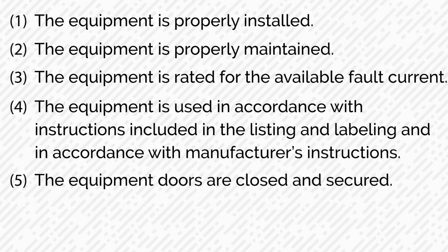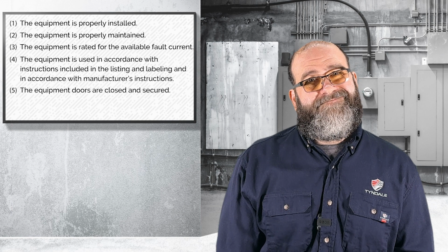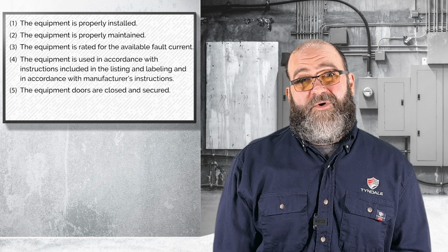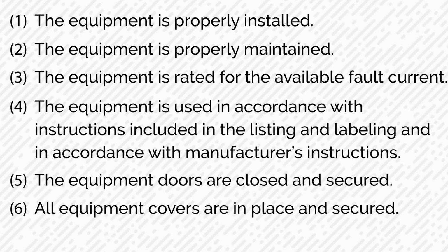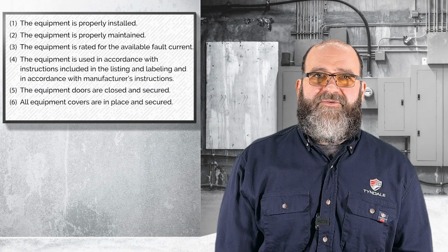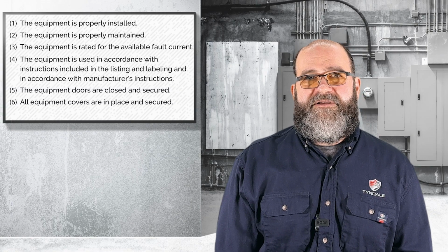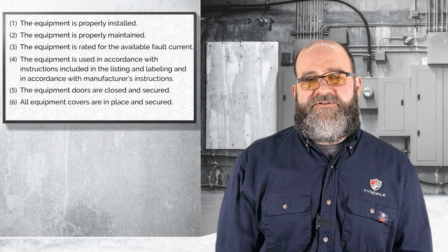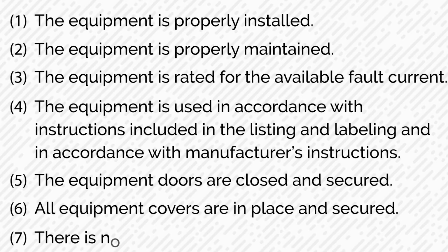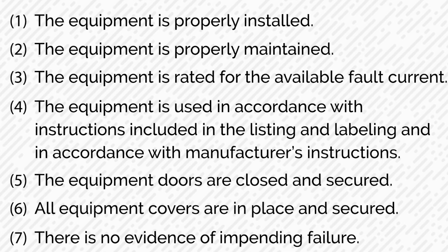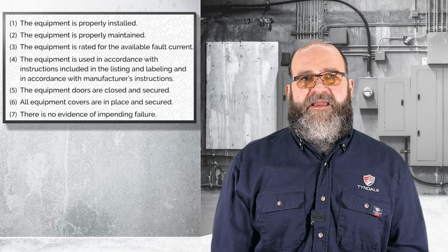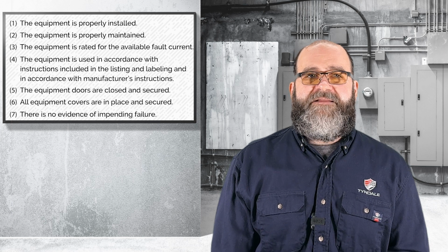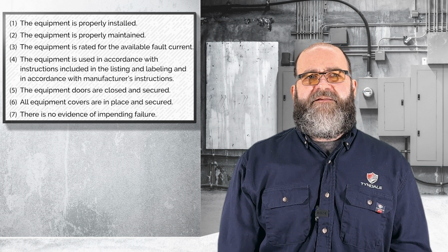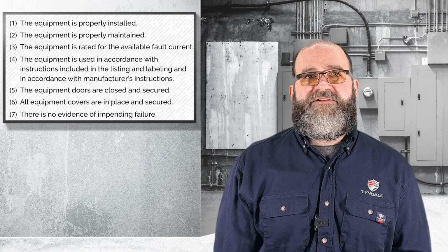Number five, the equipment doors are closed and secured. Sometimes, right? Number six, all equipment covers are in place and secured, which means all the screws installed, doors closed, everything fastened in place. Now, I don't typically see all the breaker panels having all the screws installed in the covers. That will be another issue for you. Number seven, there is no evidence of impending failure. Now, typically, you won't see that. Sometimes you'll smell that or you'll feel that heat. But number seven, I haven't found to be a large issue typically, although I have run into equipment like that.